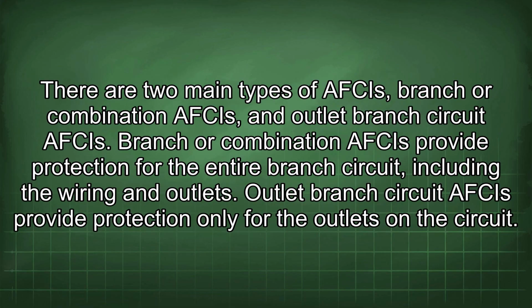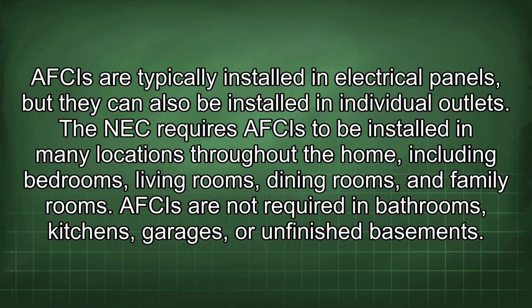There are two main types of AFCIs: branch or combination AFCIs, and outlet branch circuit AFCIs. Branch or combination AFCIs provide protection for the entire branch circuit, including the wiring and outlets. Outlet branch circuit AFCIs provide protection only for the outlets on the circuit. AFCIs are typically installed in electrical panels, but they can also be installed in individual outlets.